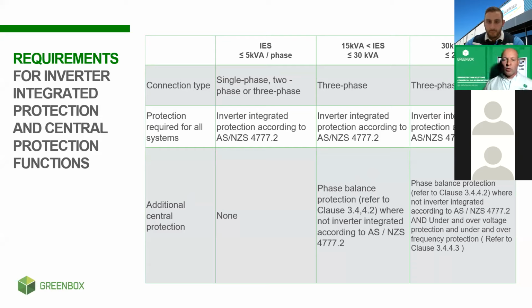I saw some questions popping up in the chat about this. People asking, if I've got a 29.9 kilowatt inverter with 35 kilowatts of solar panels, do I still require grid network protection? No, you don't, because you're still under 30 kilowatts. As soon as you put a 32 kilowatt inverter on, then you're required to install one.